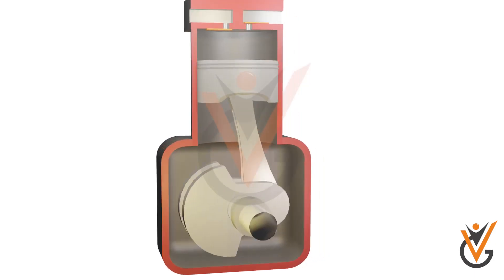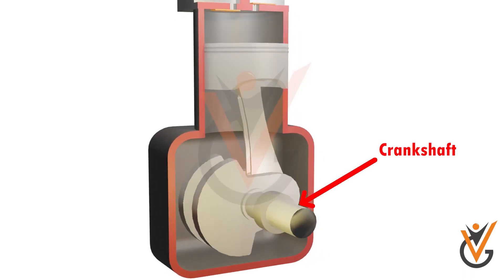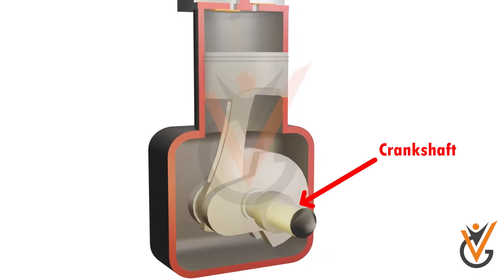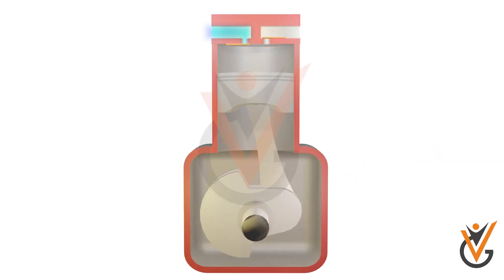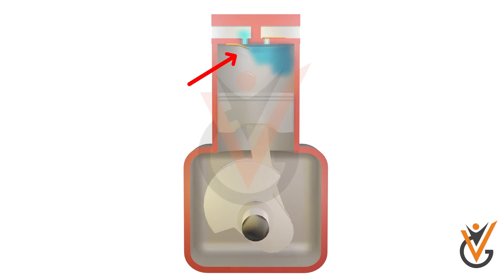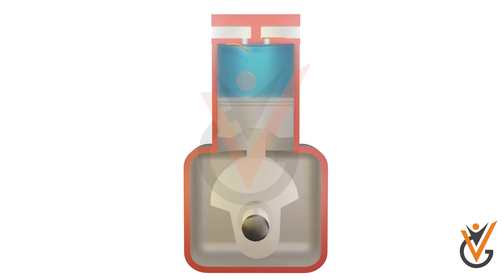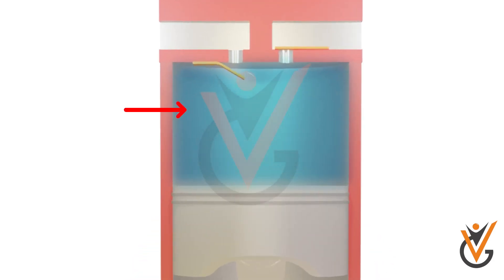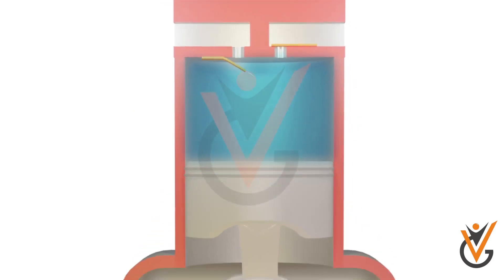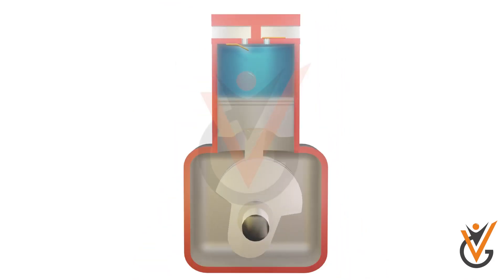The crankshaft rotates, which in turn moves the piston. The downward moving piston reduces the pressure in the main cylinder. The pressure difference will open the suction valve. The piston is taken down by the rotating crankshaft and the low-pressure air gets filled in the cylinder.